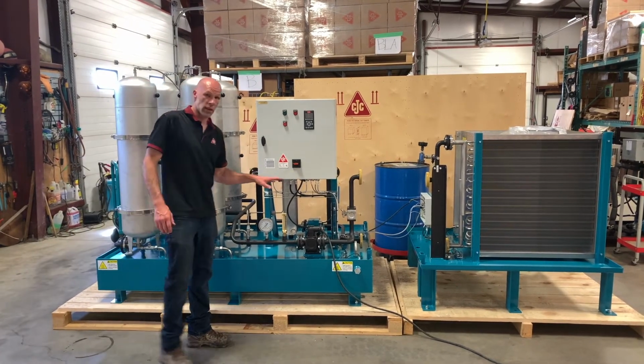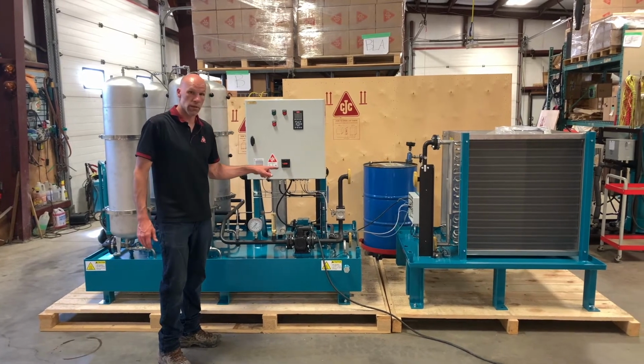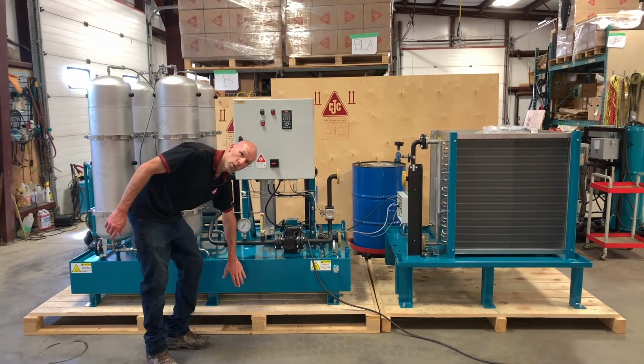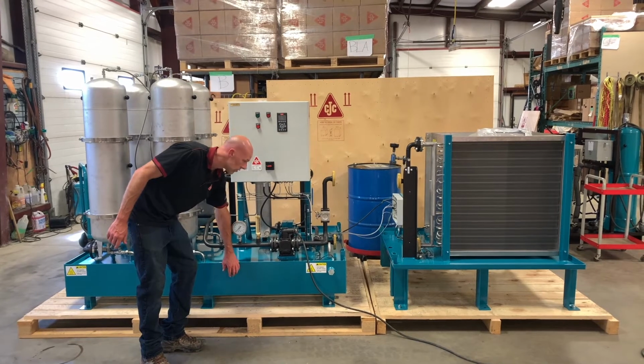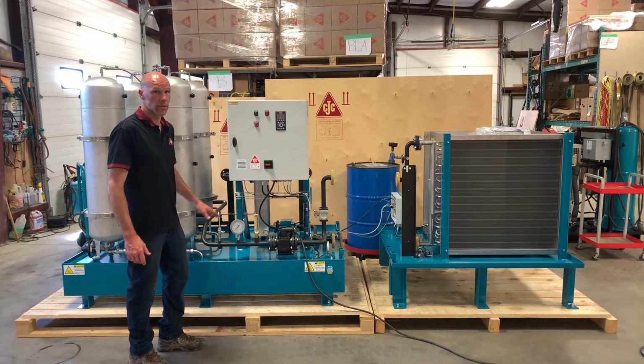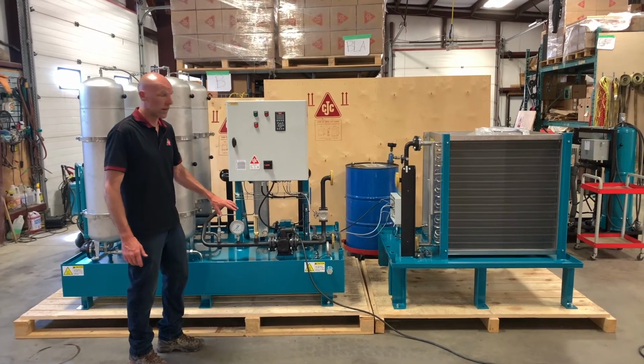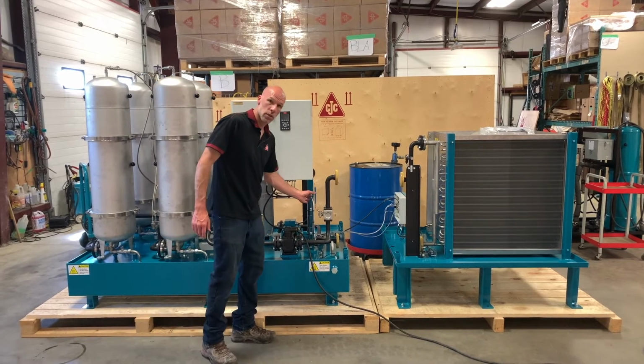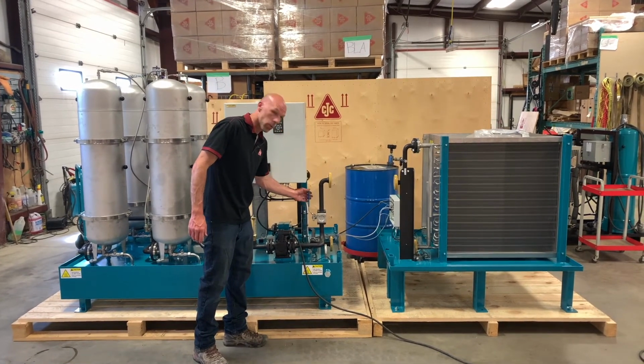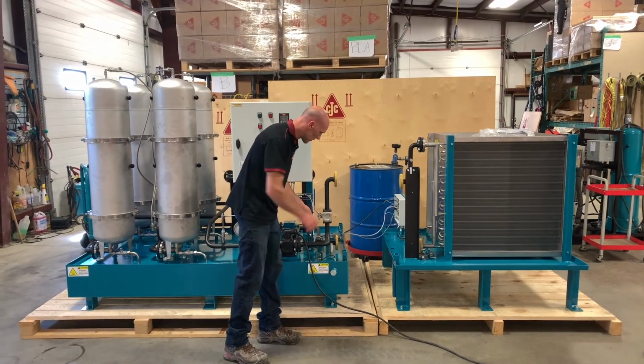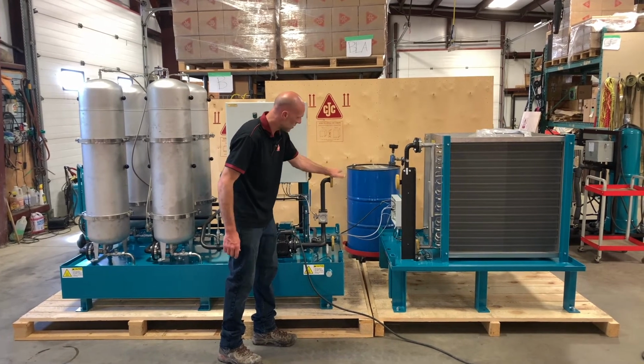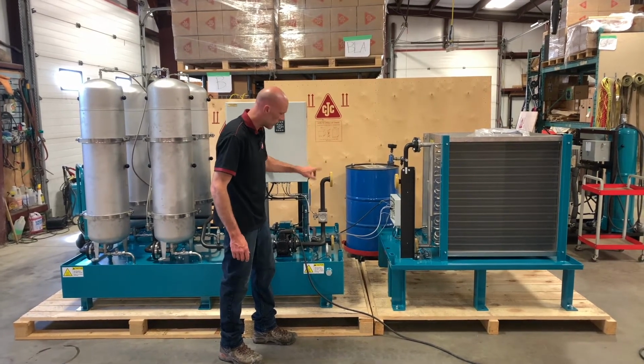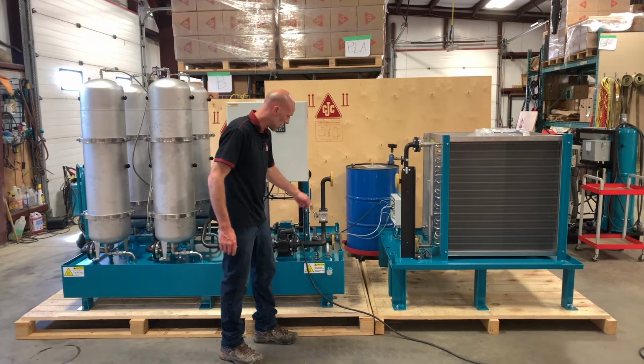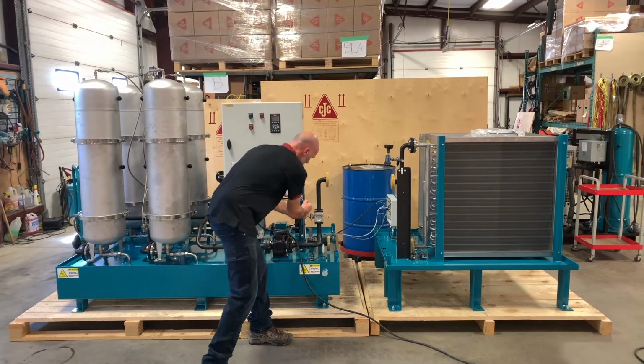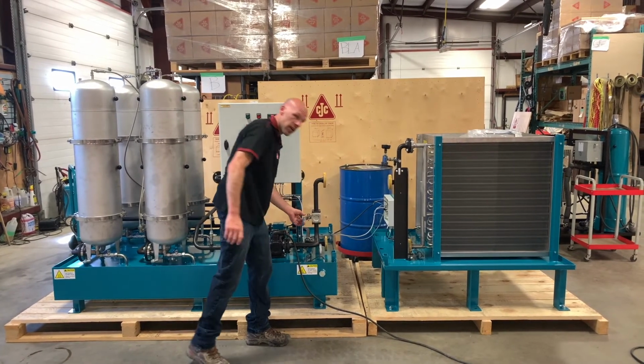And now the unit is actually built in with a three-way valve that allows you to pull the oil that you previously drained into the drain tank back up into the system. So you don't need to dispose of the oil that you've drained. You do that using the three-way valve before the pump. This is piped so that it can pull from either the cooler, which brings it in from your main system, or from the drain tank. So switch the valve to the drain tank.